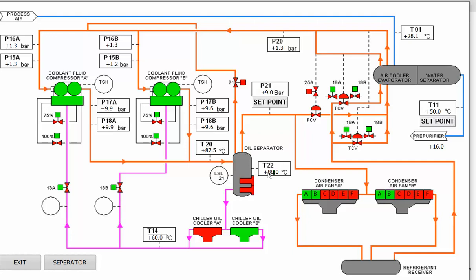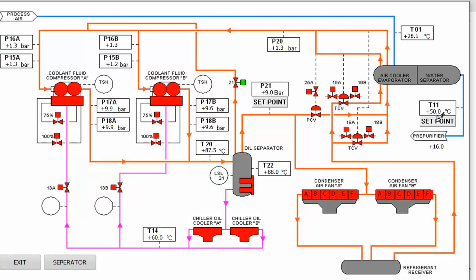The next elements I will explain are in the program — the operation of these solenoids and valves, which are heavily interwoven with the chillers. The final part will be testing the heater. In order to function-test the heater, we should shut down the chillers, or possibly disable them, so the chillers will not run even if the temperature is above the limit.